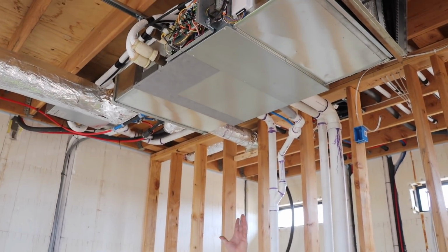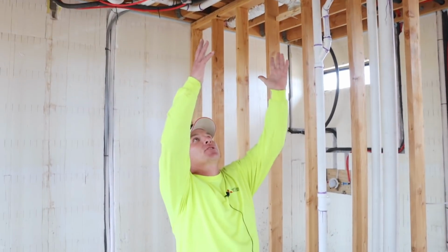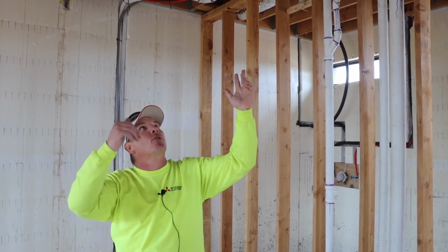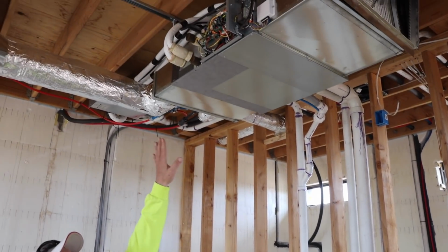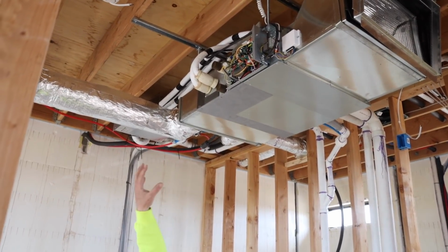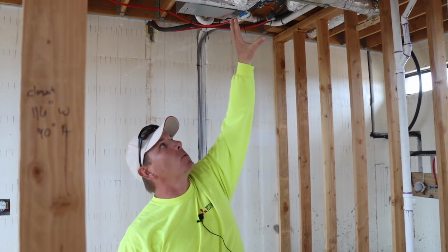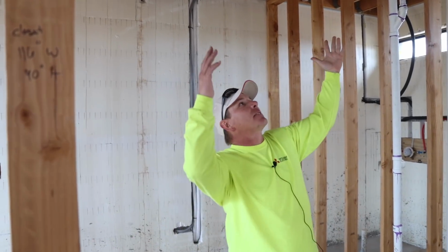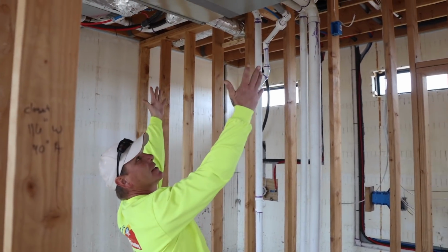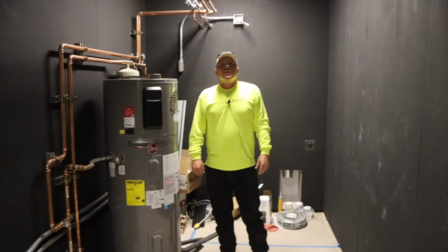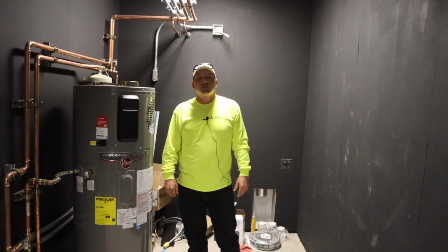That is correct. Because if you look at the bottom of this unit, we have to be able to access the entire bottom just to get to any coils, the fan motors, and blower wheels. We also need at least about 6 to 8 inches on this side of the unit to get to the main circuit boards and be able to work on it. So you just have to picture a huge access panel in here to get to this system. That's why we more recommend leaning towards attics for these units, or going with a different design like we're doing here, using a drop ceiling with removable ceiling tiles.